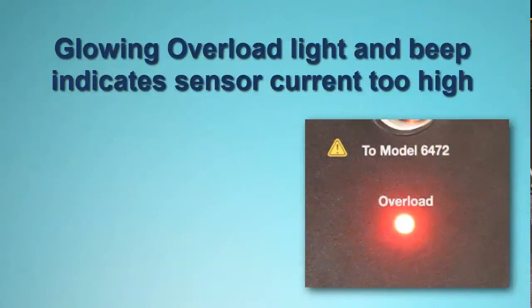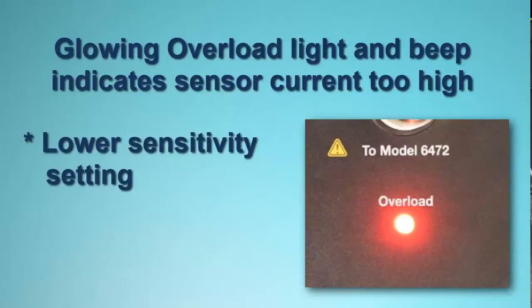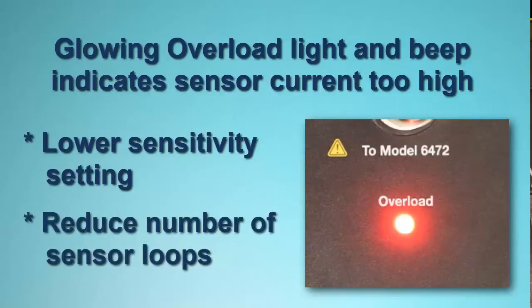Note that if the red overload light remains lit and the Model 6472 buzzer beeps, this indicates that the current in the ground flex sensors is too high for the selected sensitivity. If this happens, set the sensitivity dial to 1/10. If the condition persists, remove one loop from each sensor wrapped around the tower legs.